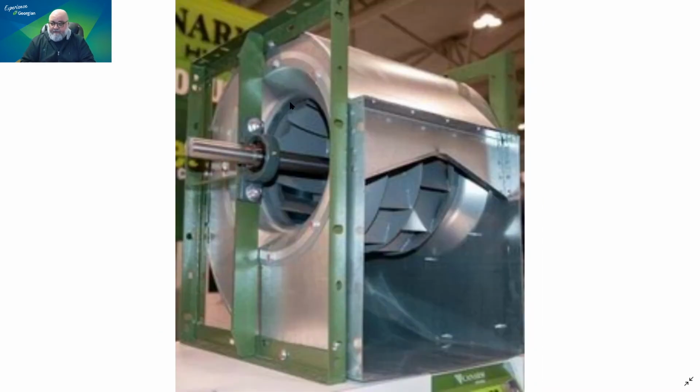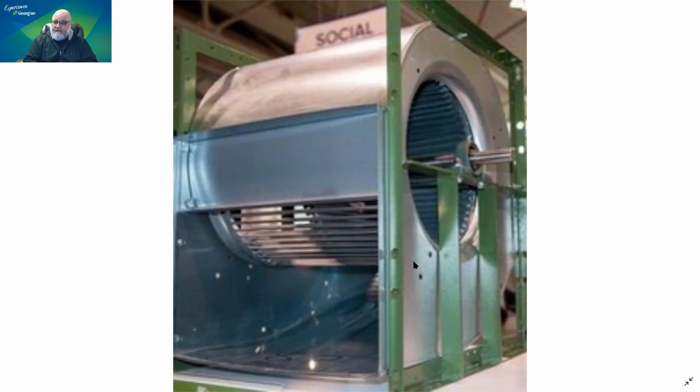That doesn't happen, I would say, not as much in a backward curved fan, where if it is given more air or less air, it doesn't matter. It has a ceiling of energy consumption that is not going to break through that drastically. So the two are necessarily different and opposite, and they serve different application needs.